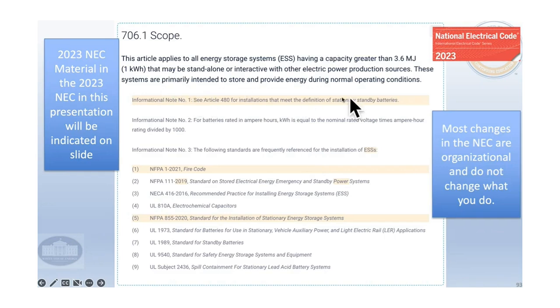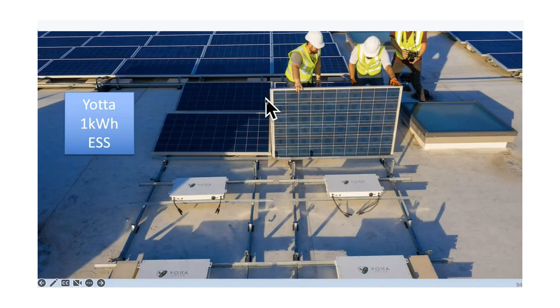So pretty much most of the changes, like I said, are organizational, but it's kind of neat to know things. This is just always interesting. There's Yotta, and I've seen them around for the last couple of years. They make these 1 kilowatt hour batteries that go underneath the modules. So it's not only an inverter for the PV, it's an inverter for the battery, and it's a ballast for the ballasted system. But there are a lot of different things to break when you have all these distributed batteries.